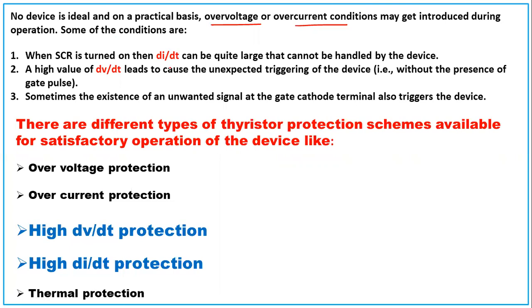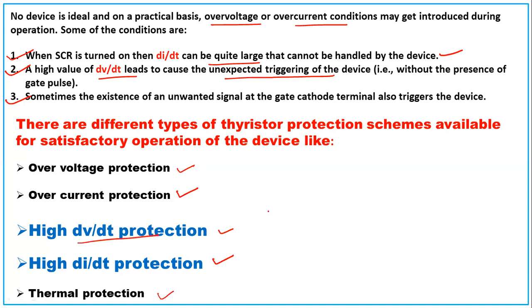Some of the conditions are: when the SCR is turned on, di/dt — the rate of change of anode current — can be quite large and cannot be handled by the device. A high value of dv/dt can also lead to unexpected triggering. There are different types of thyristor protection schemes: overvoltage protection, overcurrent protection, high dv/dt protection, high di/dt protection, and thermal protection. dv/dt and di/dt protection are the most important.